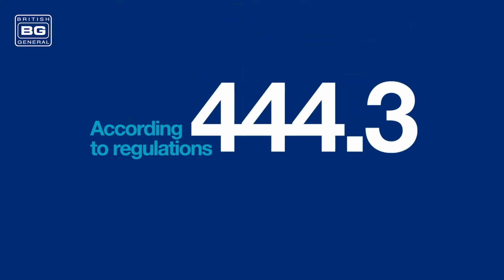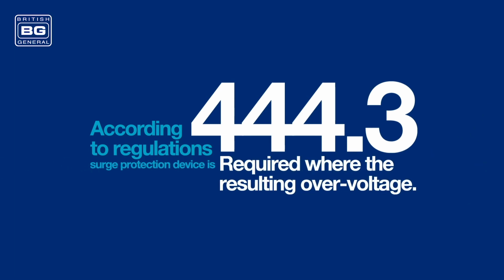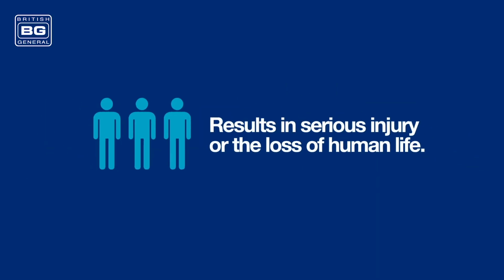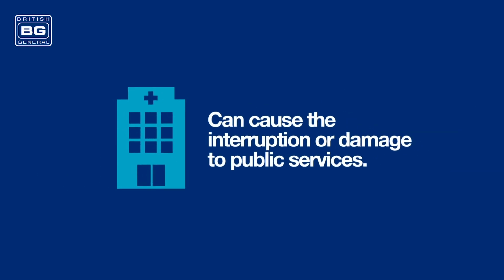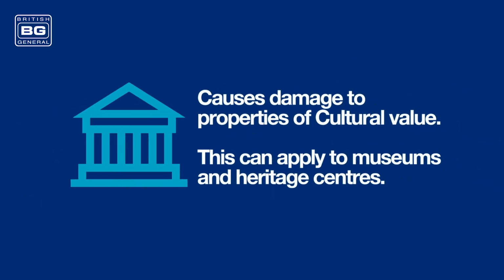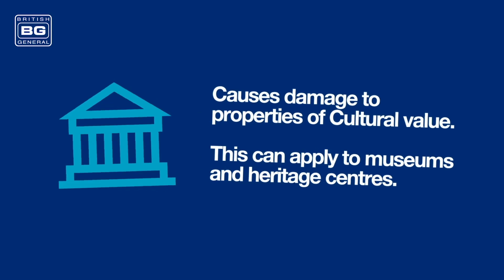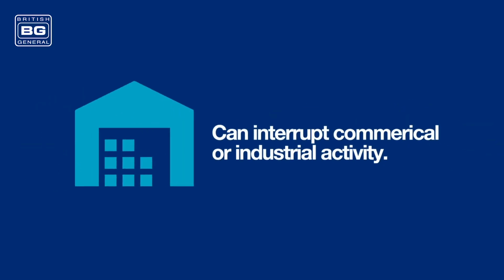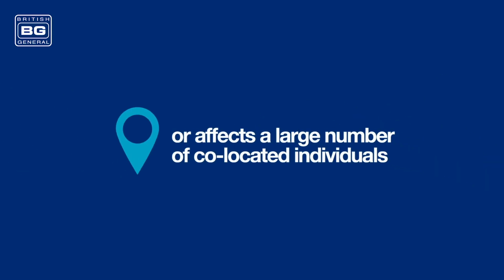According to Regulation 444.3, surge protection is required where the resulting overvoltage results in serious injury or the loss of human life, can cause the interruption or damage to public services, causes damage to properties of cultural value. This can apply to museums and heritage centres, can interrupt commercial or industrial activity, or affects a large number of co-located individuals. The regulations will make it a requirement that surge protection is used in domestic installations.